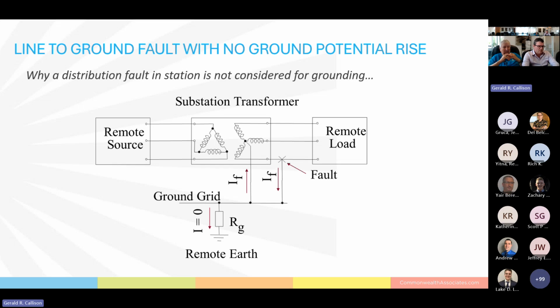Here we see this ground fault. We see a single line to ground fault on a phase where our fault current goes into the ground grid. Now this single line to ground fault current is all coming from the neutral of this transformer. So it's coming from the neutral through this phase winding to the faulted phase back into the ground grid. And it wants to get back to its source.